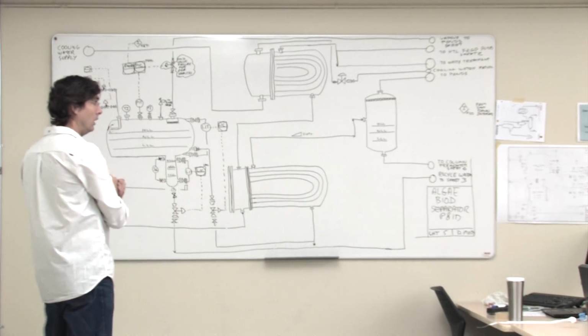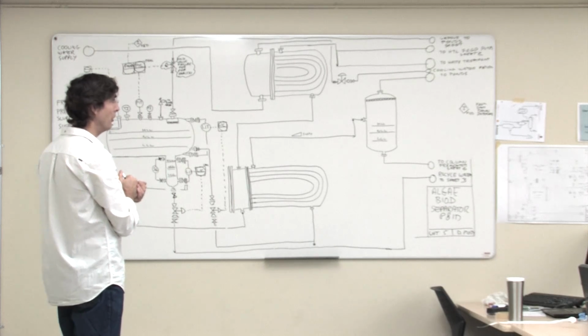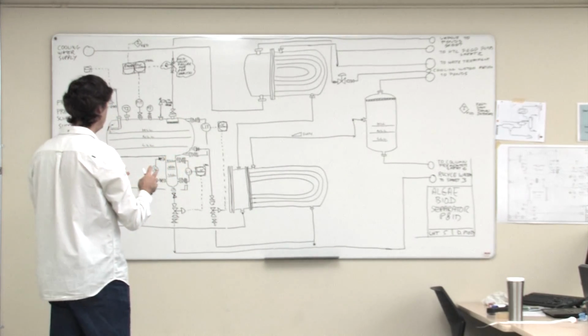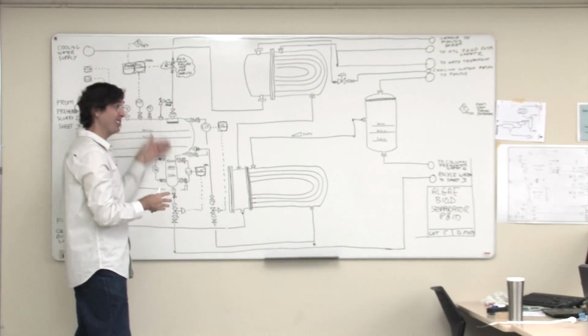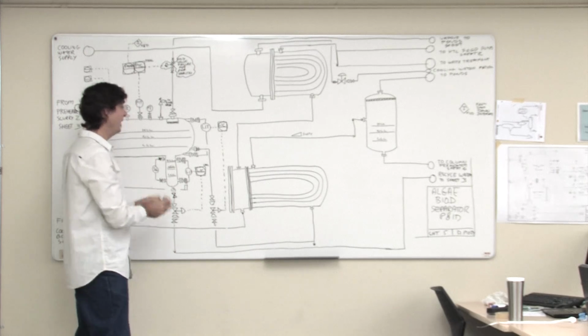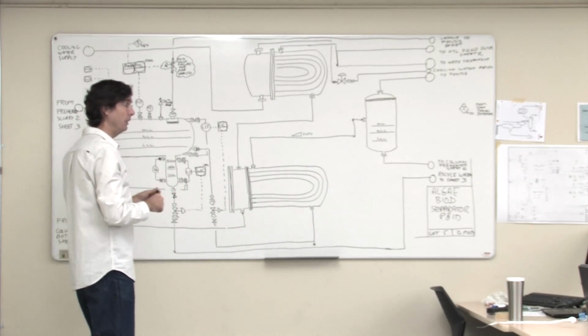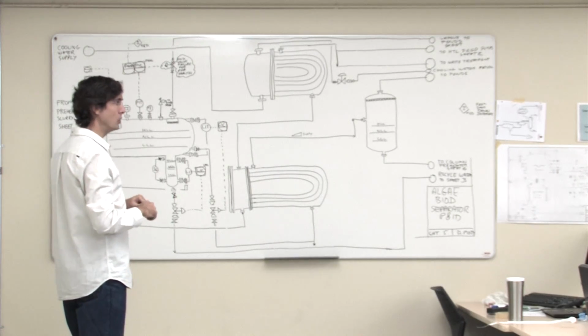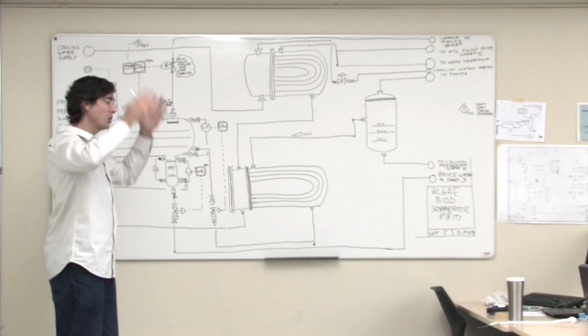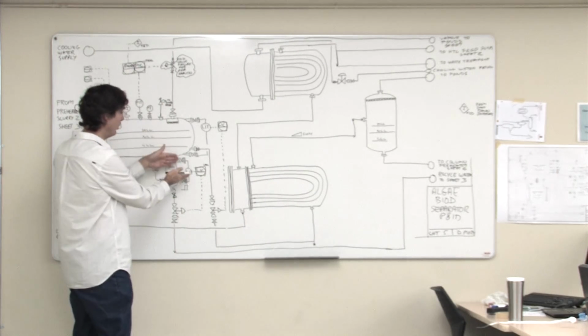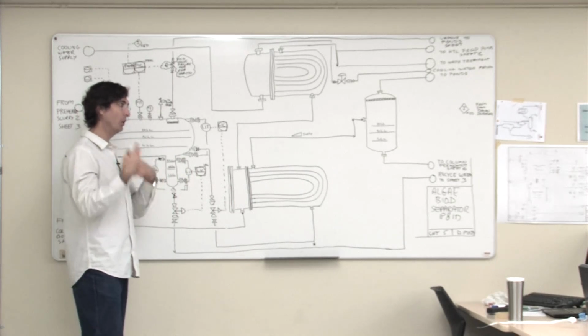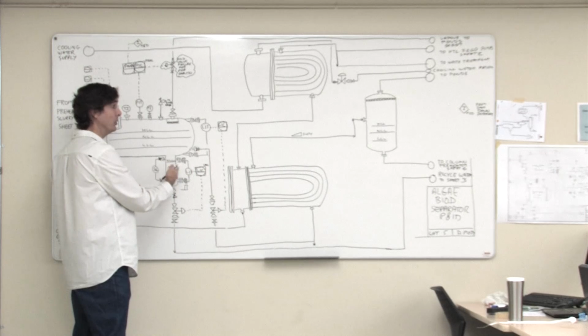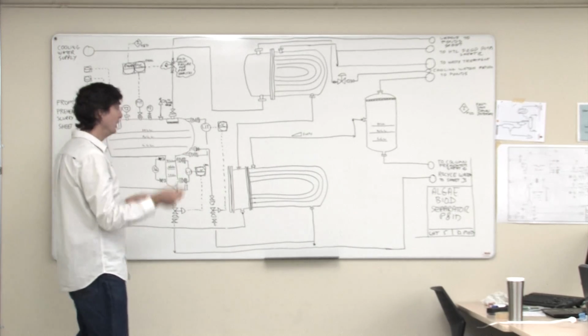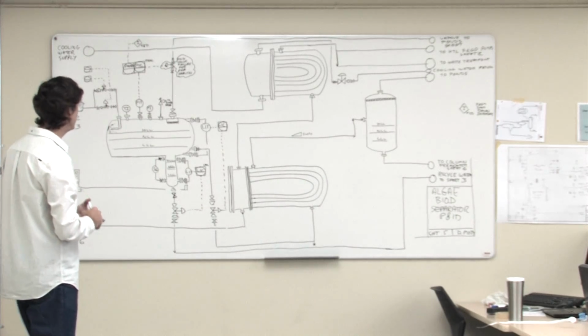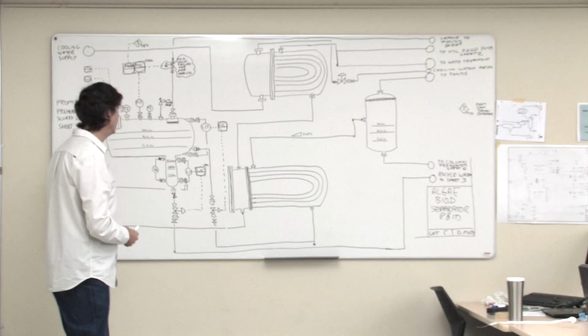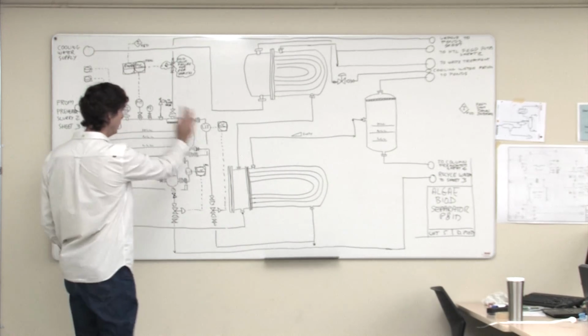So are level controllers always done by differential pressure? Not always, there's lots of different level transmitters - radar, capacitance measurement, lots of ways to do level. But this is the most common way, differential pressure, so you can probably assume you'll use that. Then the process engineer fills in a spec sheet with information about those instruments, and the instrumentation people look at those spec sheets, talk to vendors, and maybe make recommendations. They might come back and say they don't want differential pressure, they want some other technology, so you have that conversation. But at least people know you need some sort of level transmitter, and you've got the control loop defined.